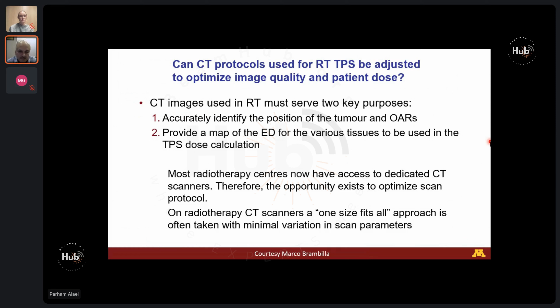We just pick a protocol for head and neck, and we just scan the patient with that one. Now, this one-size-fits-all approach has disadvantages. One is that there may be inaccuracies in the contouring, for example, but the most important one is that automatic kV selection or kV modulation is not used. We don't use that because if you change a kV, you change your CT density value, so we avoid that. There are some other new advantages out there that we may or may not use.